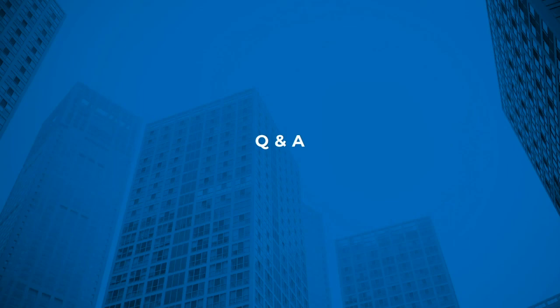All right, next question. You mentioned ionization may release some levels of ozone. What effect does this have on LEED? I haven't looked into LEED as having an effect on that, but I know LEED does take ozone into consideration, so they probably would not allow the installation of a bipolar ionization system because of LEED. The recommendation there would be to go to a needlepoint system, which has no ozone. Ultimately, we're leaning towards putting devices that have zero ozone emittance in the building anyway. The last thing we want to do is emit decent amounts of ozone through the air. So I will research that. Katie or Jake, if you could tell me who that question came from, I'd love to dive further into it and respond back to that individual.